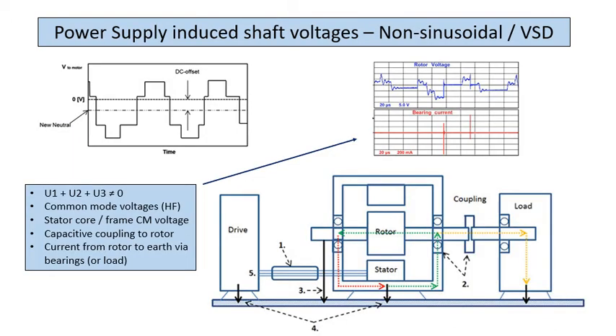And then, okay, this is pretty much Stian's presentation, that the instantaneous switching in your power devices in a VSD makes it unavoidable, really, that you have a common mode voltage, and that your stator core will be forced to adopt that voltage. And if you've got common mode currents flowing, they flow capacitively via the air gap, and if they're high frequencies and it's a small air gap, you will have reasonable current levels.